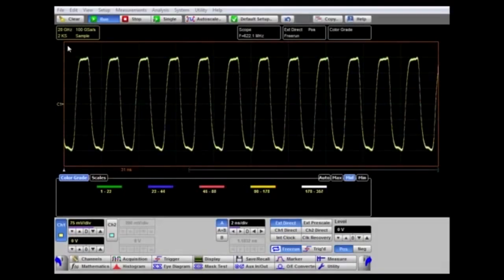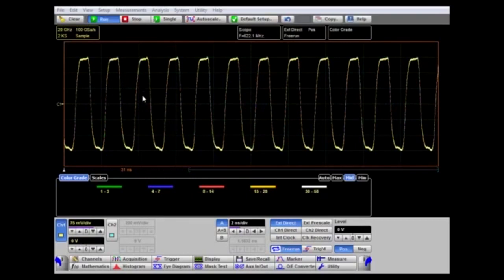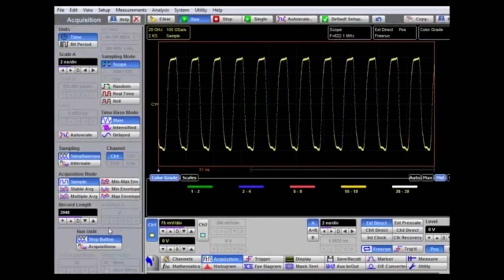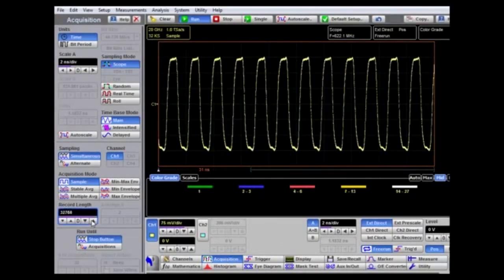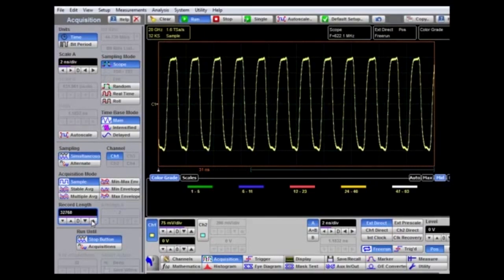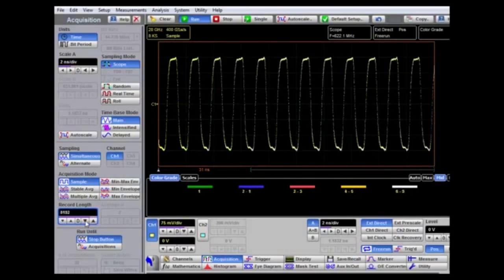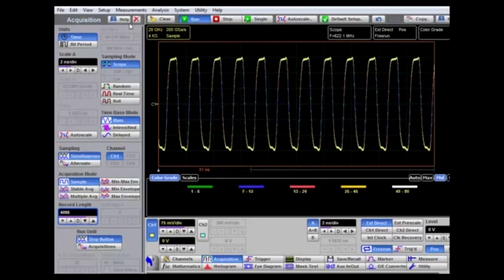It's possible to increase the record length beyond 2000 samples if more time accuracy is required. This is available in the acquisition menu, where the default value is 2048. It can be increased as high as 32,000 points in this instrument, but there is a trade-off: the longer the record length, the longer it takes to acquire the data. In this case, I'll select a 4096 record length.